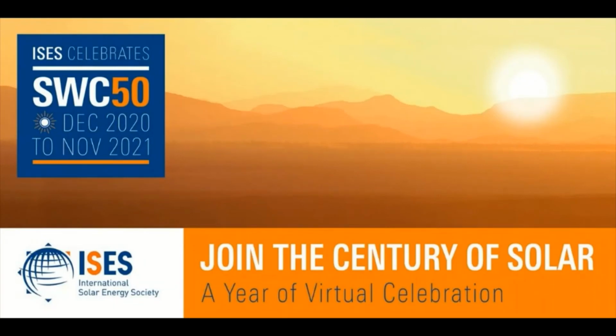What I will say, which was a major conclusion from my dissertation: if you're comparing solar thermal with a grid-powered heat pump, and you're able to operate your heat pump over 3,000 to 4,000 hours per year, then the heat pump is generally the better way to go. But if you can only operate it 1,000 to 2,000 hours a year or less, then solar thermal tends to be the better option.